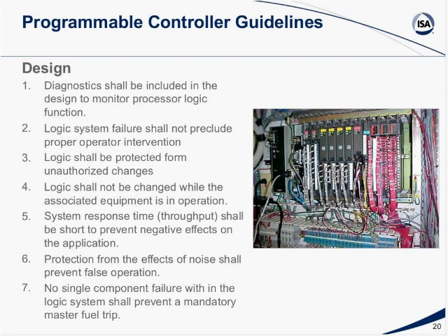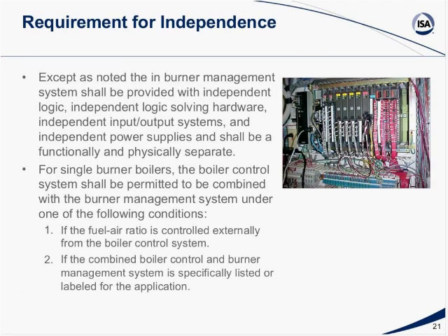System response time, or the throughput of the logic system, shall be short to prevent negative effects on the application. Protection from the effects of noise shall prevent false operation. That can be noise not only from the circuitry, but also from using walkie-talkies or some other device that may cause a problem in the safety system. In other words, no single element or component within the logic system shall prevent a mandatory master fuel trip. You cannot have any kind of bypass that will keep you from going into fuel trip if you have a problem. So no fuel trip can be bypassed.